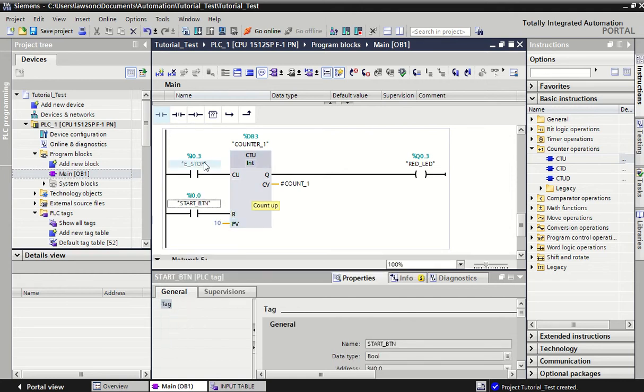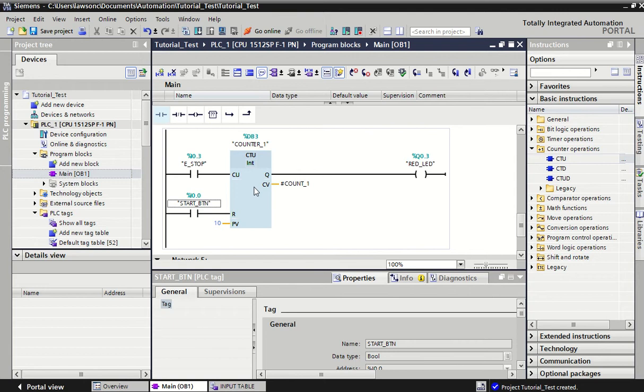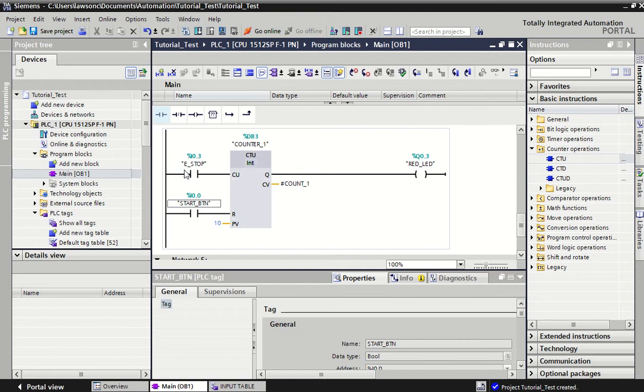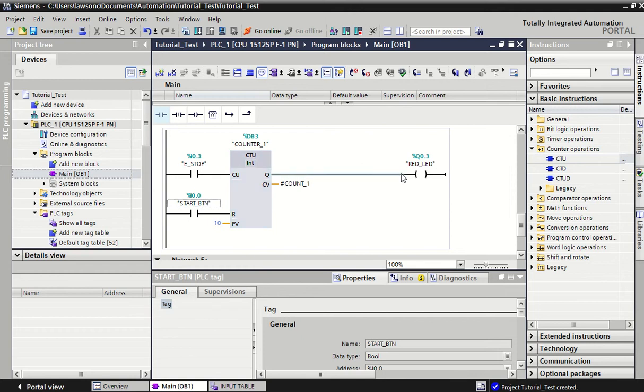So let's talk about this. When the e-stop gets triggered, power will flow into the counter and become energized. When the e-stop is released, the counter is no longer energized. That implies one count has been reached. The input must come on and come off to get a count, so it must be pulsed - turn on and turn off. That will be one count. Your current value will go to one when that happens.